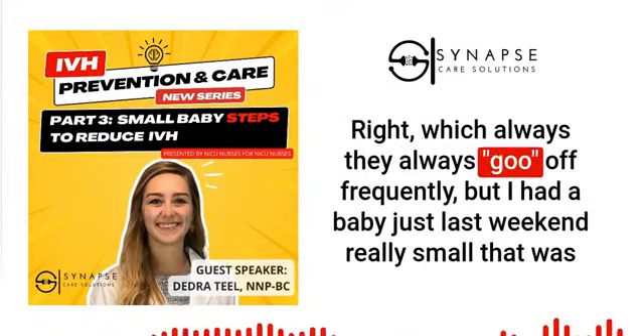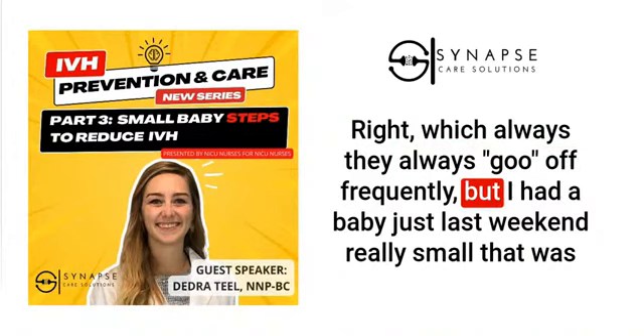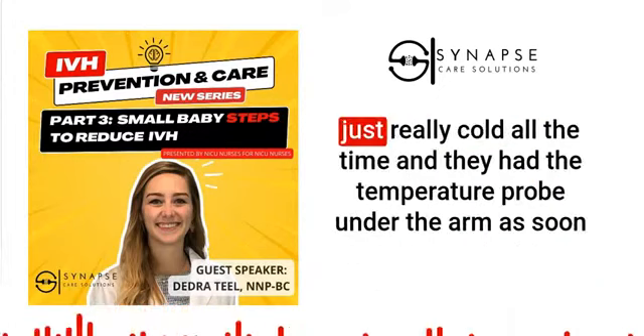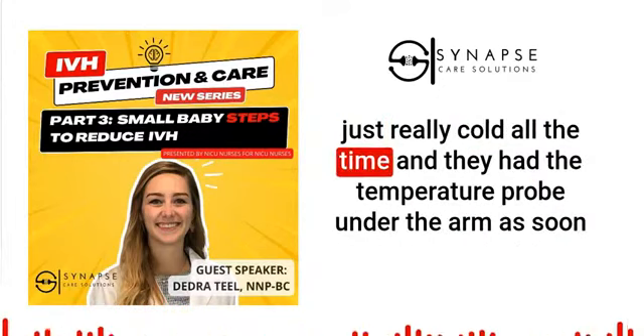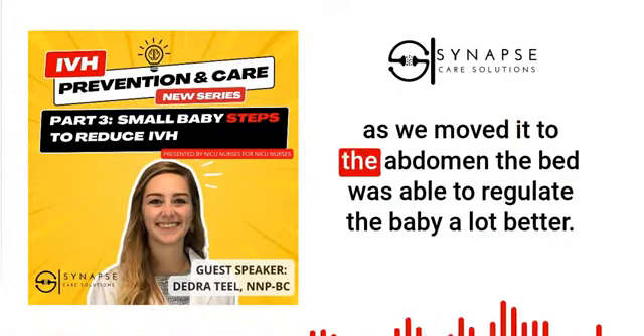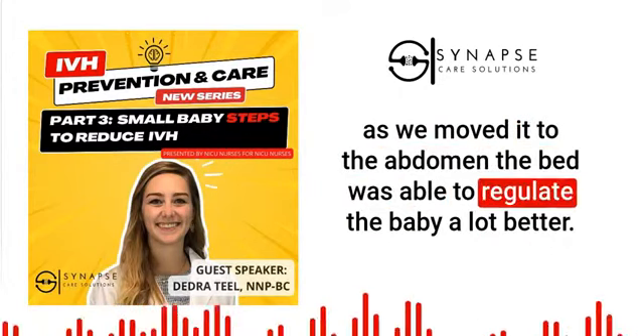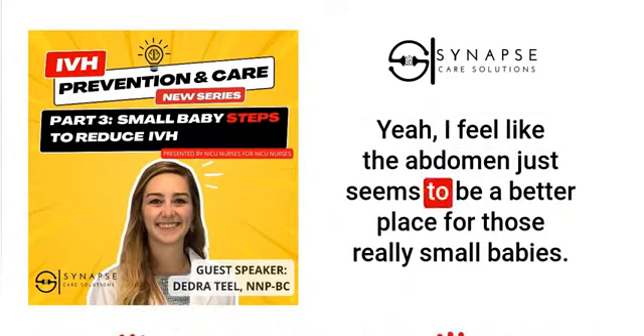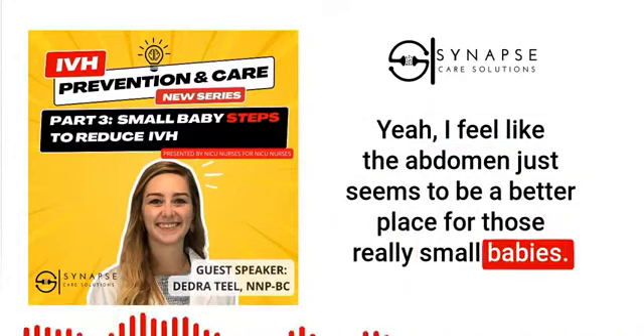Which they always go off frequently, but I had a baby just last weekend, really small, that was just really cold all the time, and they had the temperature probe under the arm. As soon as we moved it to the abdomen, the bed was able to regulate the baby a lot better. Yeah, I feel like the abdomen just seems to be a better place for those really small babies.